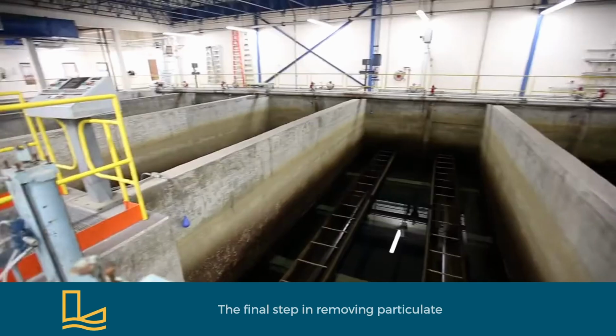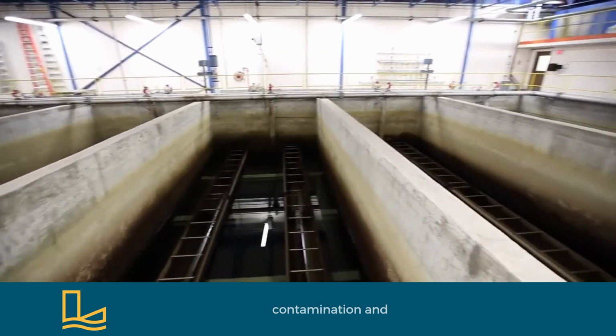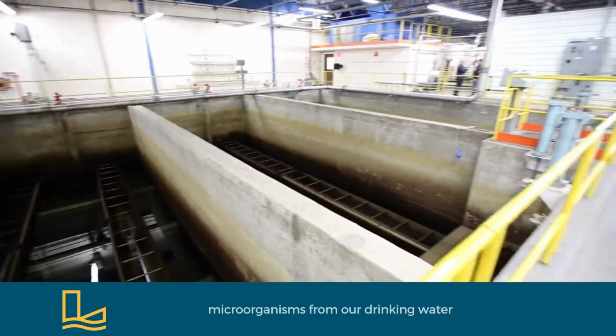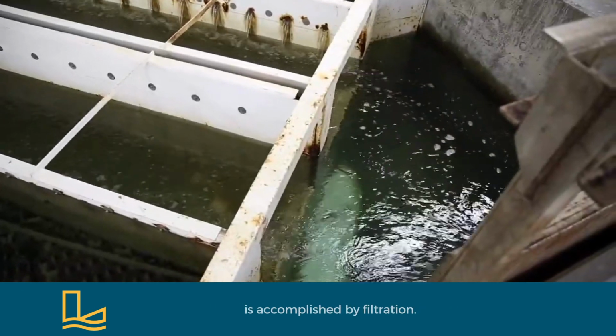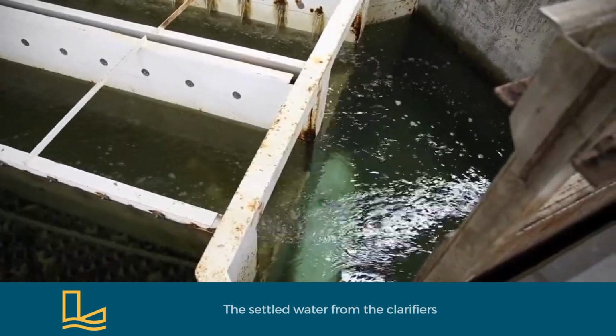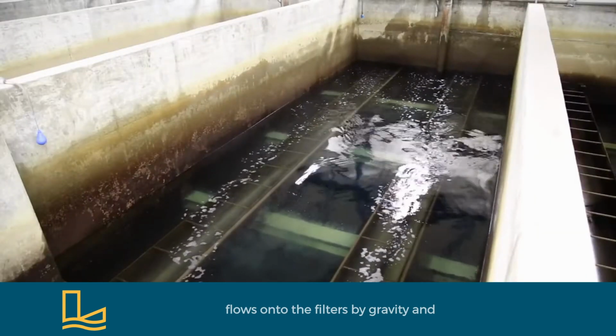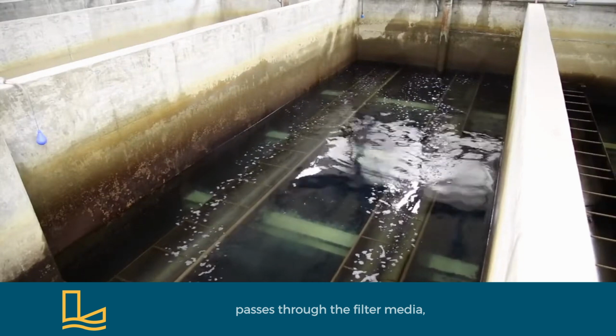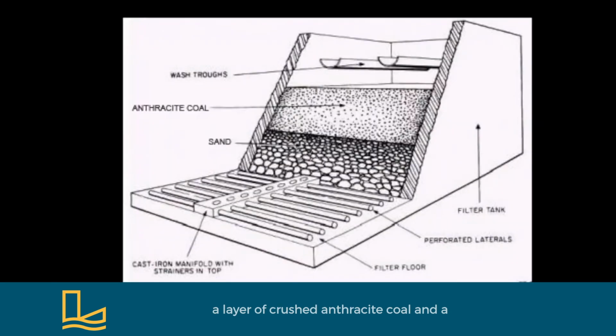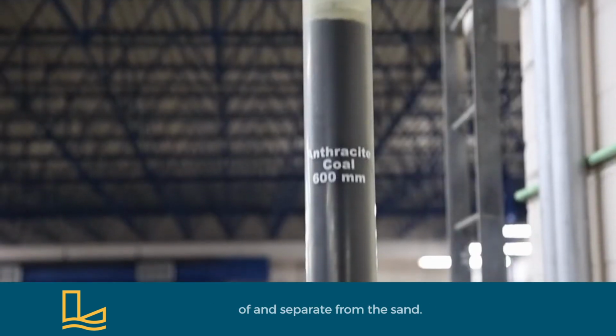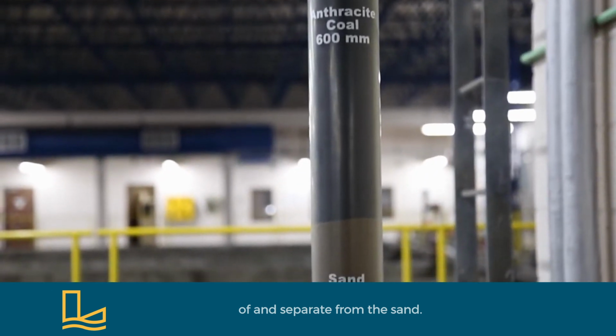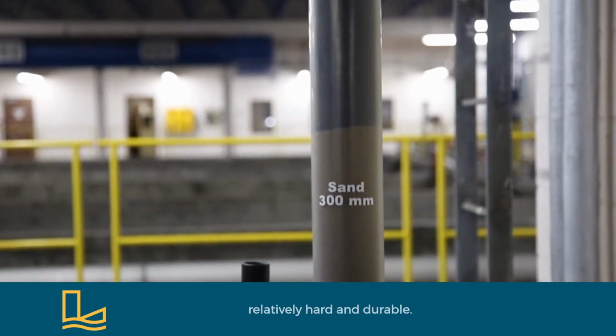The final step in removing particulate contamination and microorganisms from our drinking water is accomplished by filtration. The settled water from the clarifiers flows onto the filters by gravity and passes through the filter media, a layer of crushed anthracite coal and a layer of sand, before exiting the bottom of the filter. Anthracite coal is used because it is lighter than sand and will remain on top of and separate from the sand. Anthracite is also relatively hard and durable.